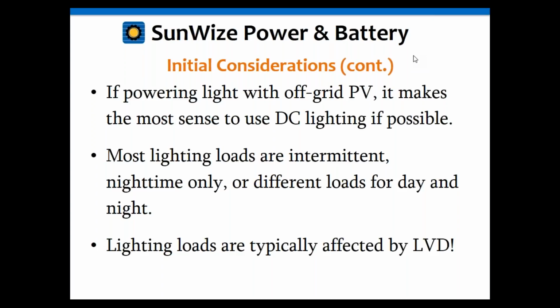Also, something else to consider is that with lighting loads, most of the controllers do have a low voltage disconnect feature, which basically means if you have depleted the batteries too far, it will disconnect the load to protect the battery. This is important in critical loads. If you have a non-critical load, you may not care, and you may go, that's fine. It's okay if the light goes out at 4 o'clock in the morning, nobody may care. But if you're on an obstruction light or navigational type of beacons or something like that, you may want to make certain that those operate all the time. So you may make certain that you oversize the system to compensate for that. We'll touch on that a little bit more when we talk about the basic system sizing, because in the basic system sizing, we do go through critical and non-critical loads.